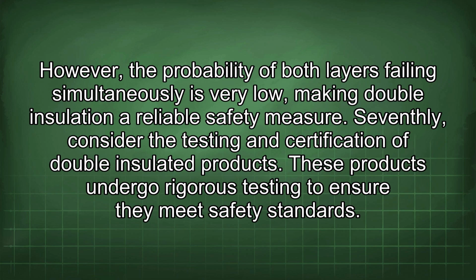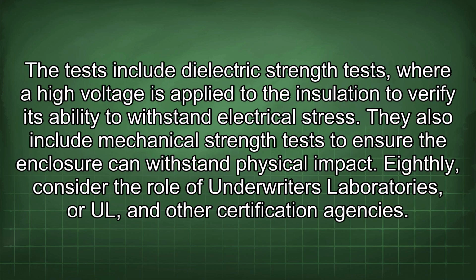Seventhly, consider the testing and certification of double insulated products. These products undergo rigorous testing to ensure they meet safety standards. The tests include dielectric strength tests, where a high voltage is applied to the insulation to verify its ability to withstand electrical stress. They also include mechanical strength tests to ensure the enclosure can withstand physical impact.